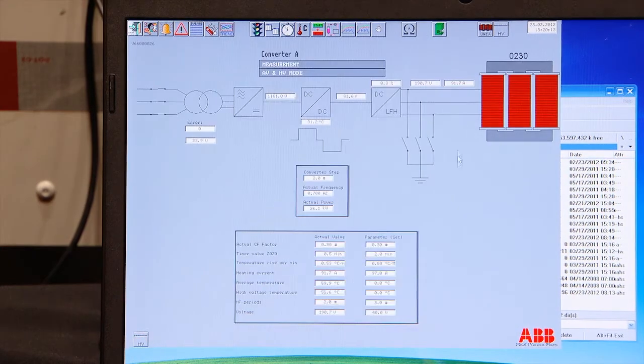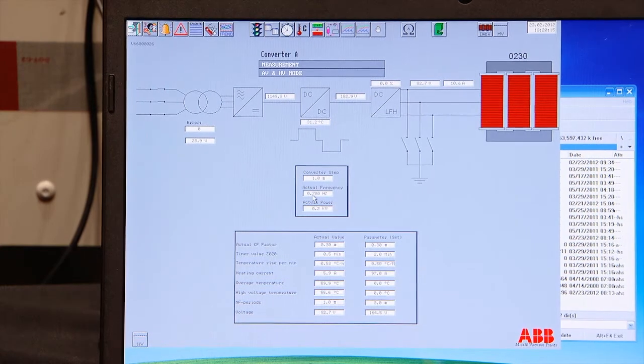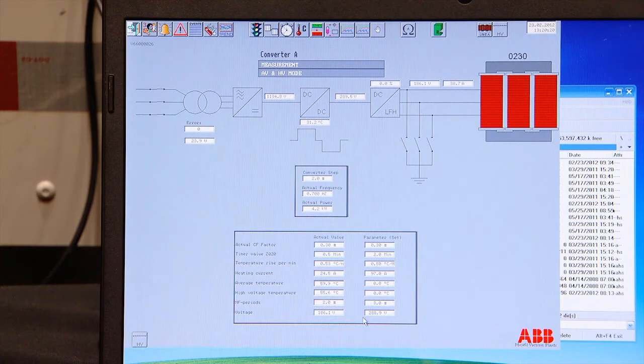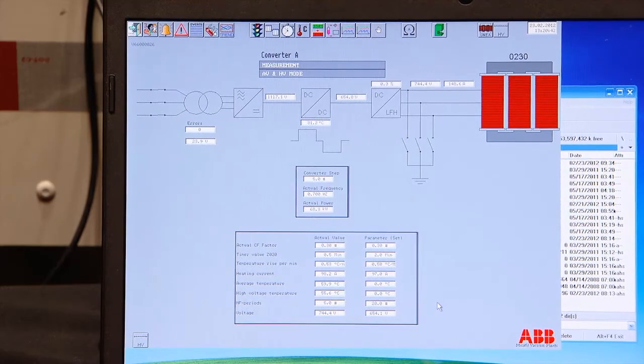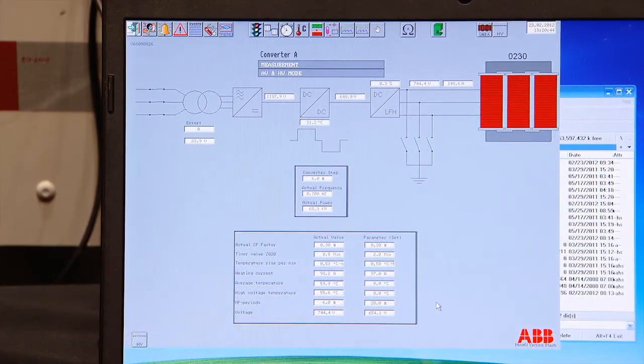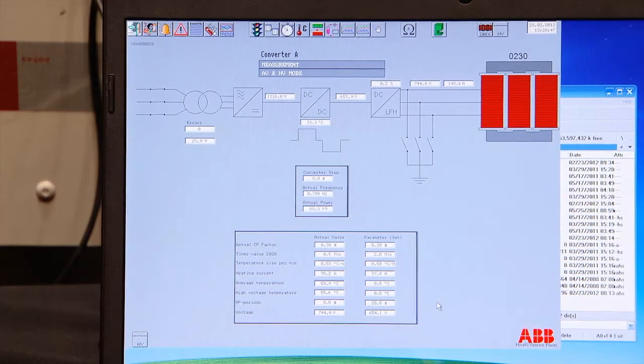We are coming back to our normal frequency, and we do now what's called a demagnetization. You are stepping up the voltage in cycles of three cycles at each voltage level, and up to the highest voltage level where we will run 20 cycles. And this is to even out the magnetism in the transformer. During the high voltage measurement, you're feeding a lot of magnetism into one leg, which means that if you directly start taking the measurement, you will have a very uneven balance between the windings.